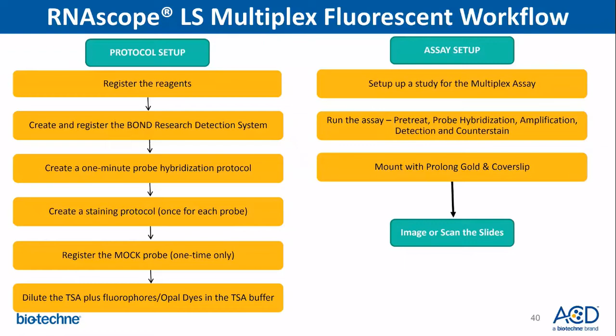The LS multiplex assay runtime is about 14 hours. Please note that the kits provided are enough to stain 60 slides, whereas the probes are sufficient to stain only 30 slides. So please keep that difference in mind. And please note that a Bond Research detection system from Leica would be required for performing the LS multiplex fluorescent assay. Again, signal detection is performed using Opal dyes or TSA Plus fluorophores, which need to be purchased separately from Akoya Biosciences. And then if you're doing a 4-plex detection, then a 4-plex ancillary pack will be required.